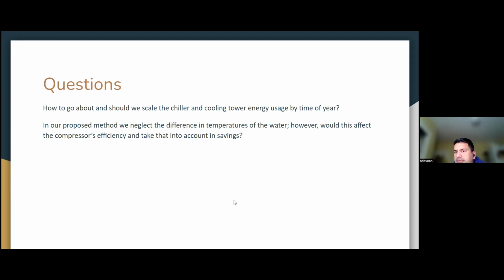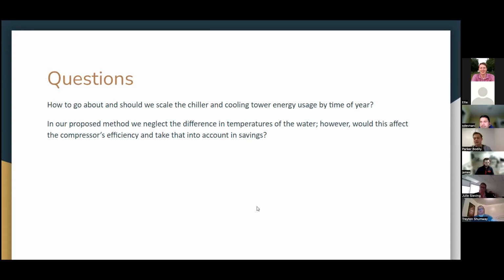Did that help anybody? Or have I lost you completely? I think it makes sense to me, and it helped a lot determining how much energy is being used, and also with the time of year. I think it helped a lot. Okay, so your chiller is going to run that way. That's for your chiller, because all you need is a kW per ton as temperature varies, right? Wet bulb temperature or dry bulb temperature.